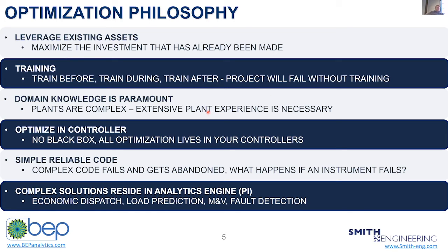So we believe that if it's simple machine control, it should be done within the BAS controller for multiple reasons. There shouldn't be costs into perpetuity on simple logic. You should own it. And at the end of the day, you're going to have a local relationship with a controls tech that's going to need to be able to get into that controller and modify this stuff on the fly if there's an emergency or something like that. And that leads me to the next one. The code needs to be simple and reliable.